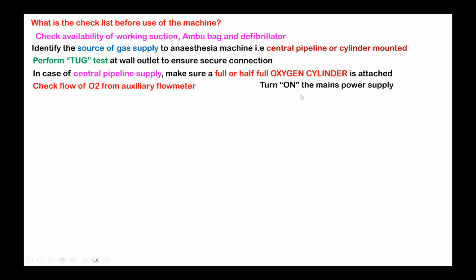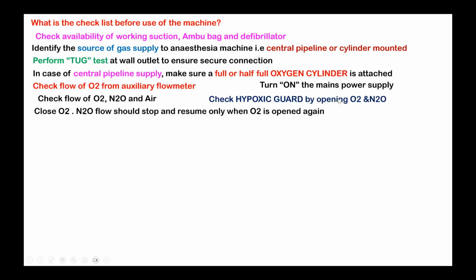Turn on the main power supply in case of a workstation. Check flow of oxygen, nitrous oxide and air. Check the hypoxic guard by opening oxygen and nitrous oxide. Then close oxygen, and nitrous flow should stop. That is how you check the hypoxic guard.